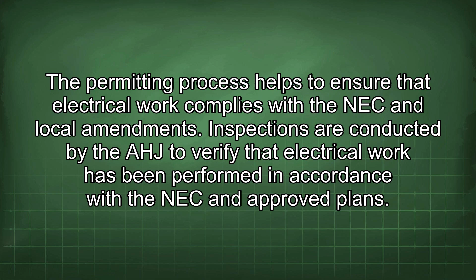Inspections are conducted by the AHJ to verify that electrical work has been performed in accordance with the NEC and approved plans. Inspections are typically performed at various stages of construction, such as after rough wiring and before covering up wiring. Addressing any deficiencies identified during inspections is crucial to obtain final approval.